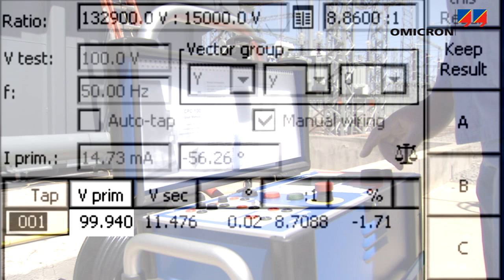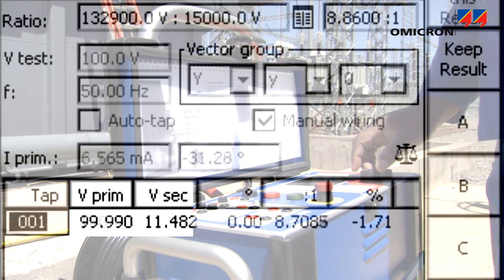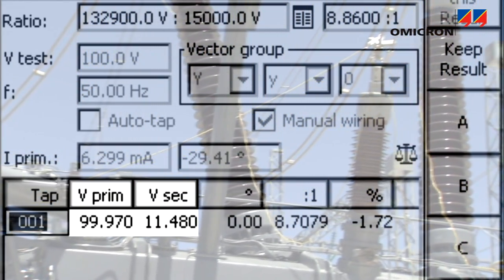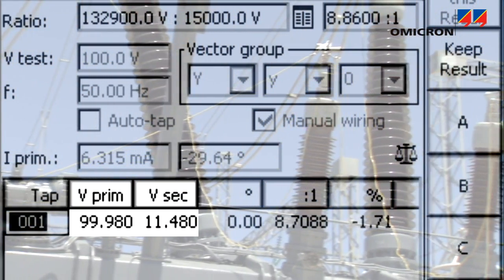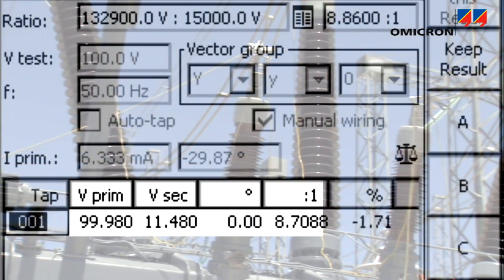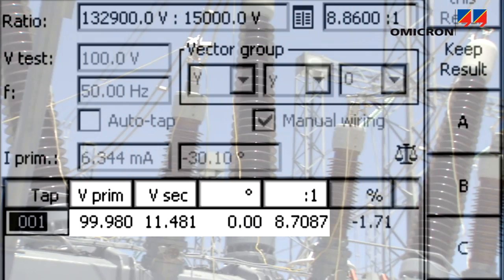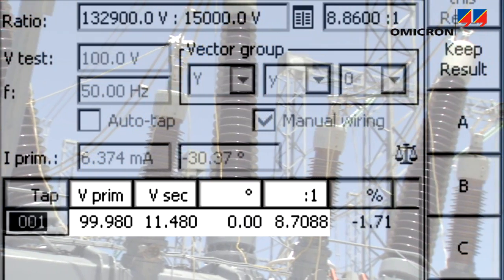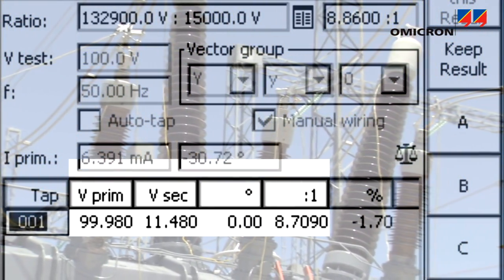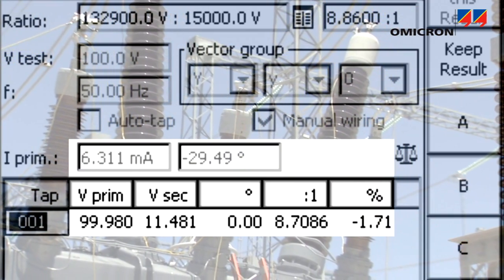The applied voltage and the load current are measured internally. The secondary voltage is connected to the CPC's voltage measurement input. All quantities are measured in amplitude and phase. The ratio of these voltages, equaling the turns ratio, is calculated and displayed, along with the magnetizing current, and the deviation from the nominal ratio is displayed.